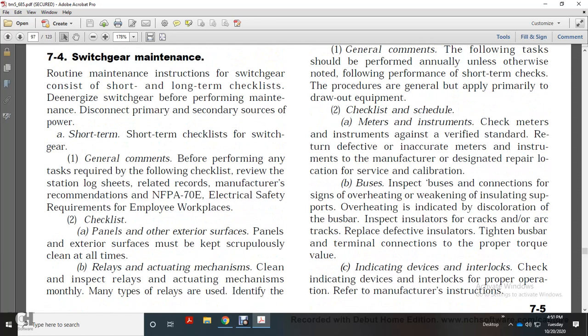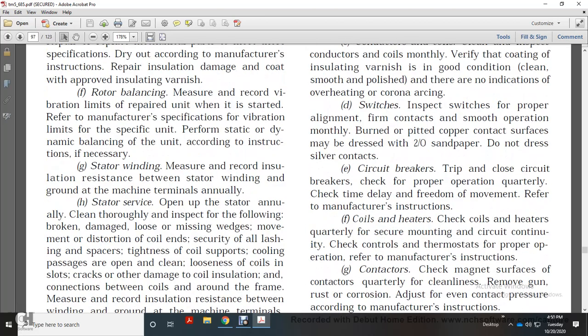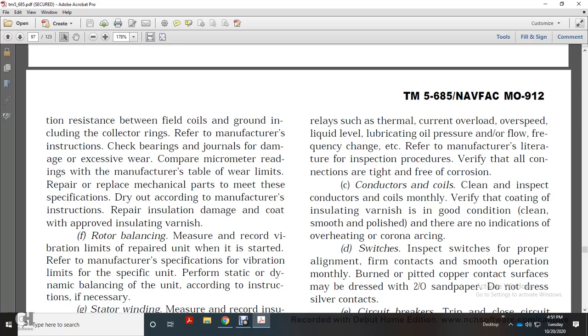Panels, other exterior surface of the panels. Exterior surfaces must be kept scrupulously clean at all times. Relays, actuating mechanism: clean and inspect relays and actuating mechanisms monthly. Many times relays are used and identified as relays such as thermal, current overload, overspeed, liquid, oil, oil pressure, and flow, with the frequency per the preferred manufacturer literature inspection procedure.